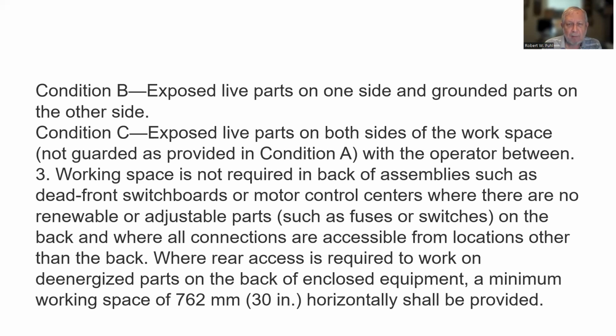Condition B, exposed live parts on one side and grounded parts on the other. Condition C, exposed live parts on both sides of the workspace, not guarded as provided in condition A, with the operator between.